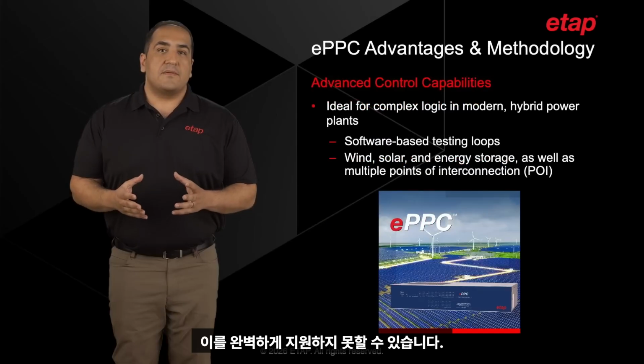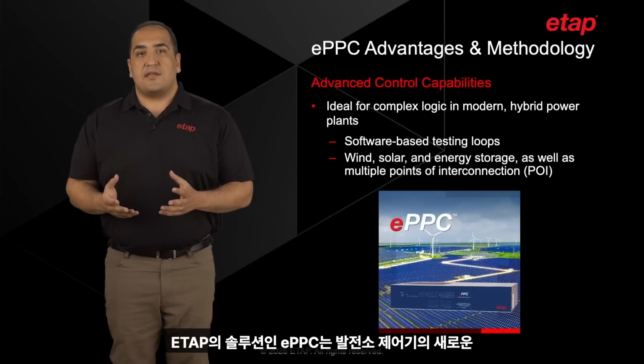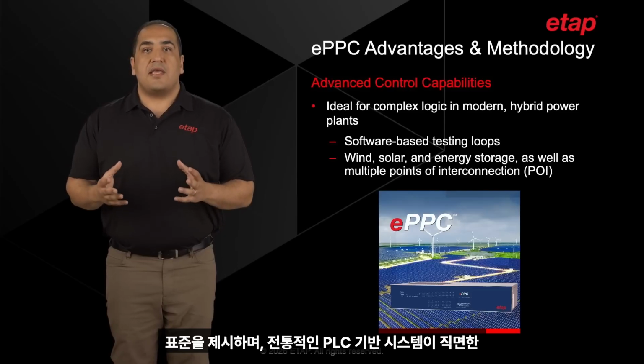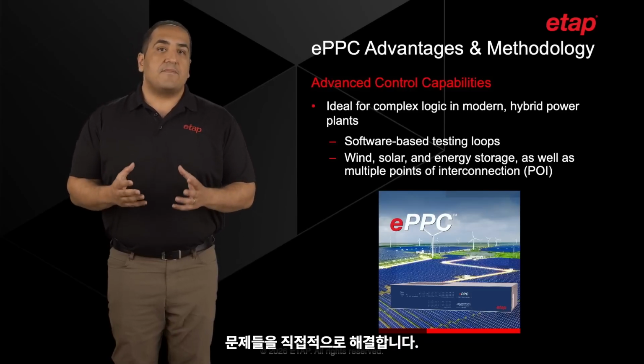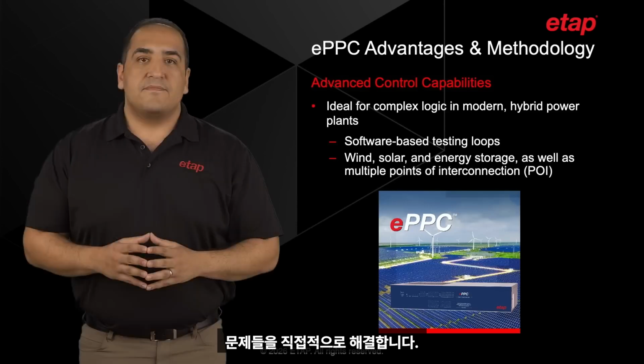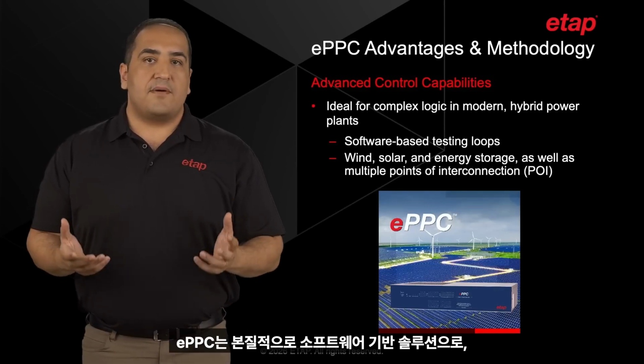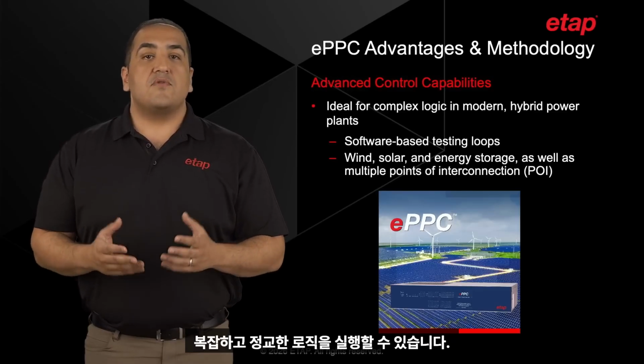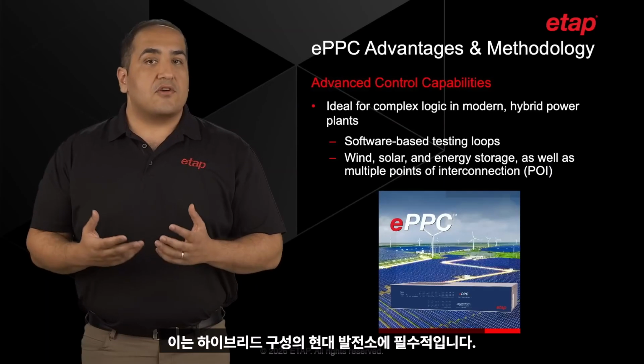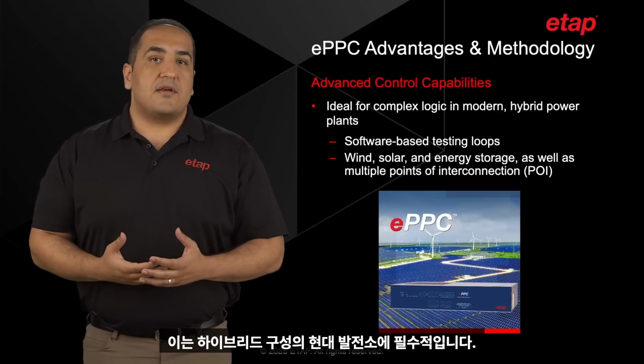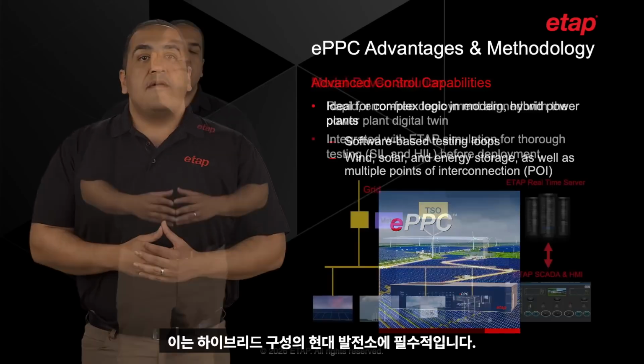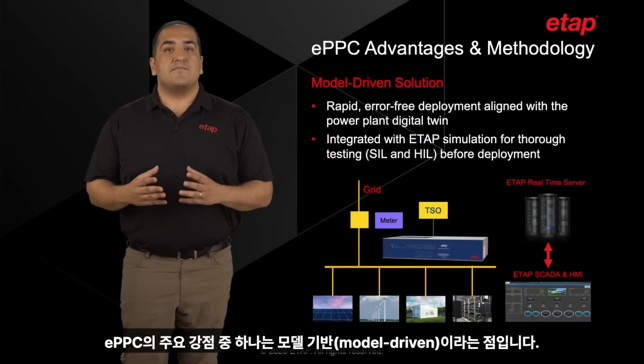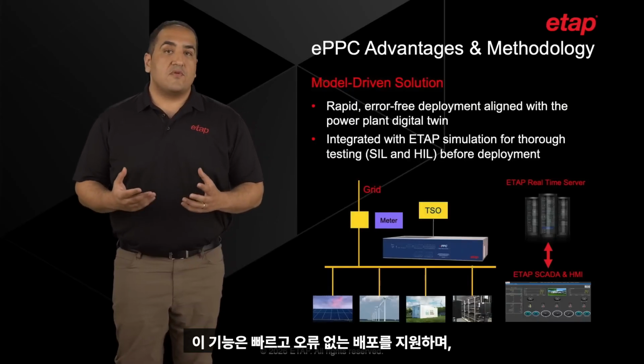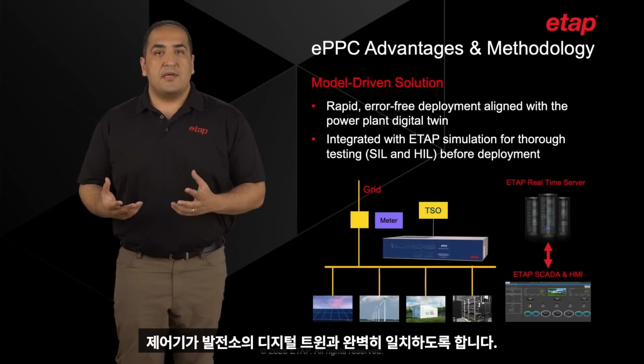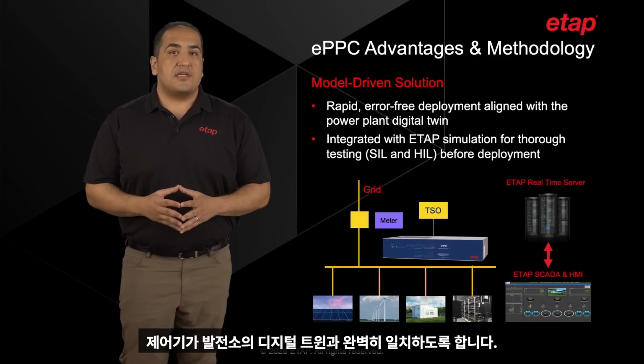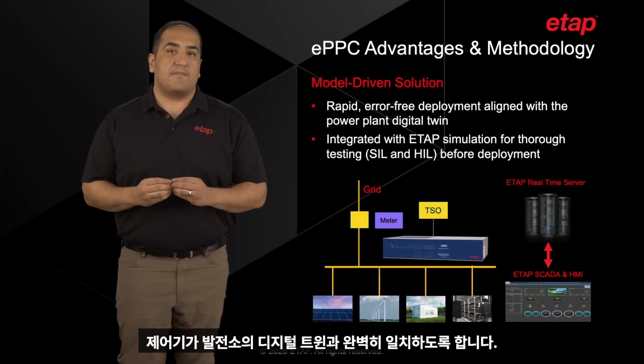Our ETAP solution, the ePPC, sets a new standard in power plant controllers by directly addressing the challenges that traditional PLC-based systems often face. At its core, ePPC is a software-based solution, which allows it to execute complex and sophisticated logics that are crucial for modern power plants, particularly those with hybrid configurations. One of the key strengths of ePPC is its model-driven nature. This feature not only enables rapid and error-free deployment, but also ensures that the controller is perfectly aligned with the digital twin of the power plant.